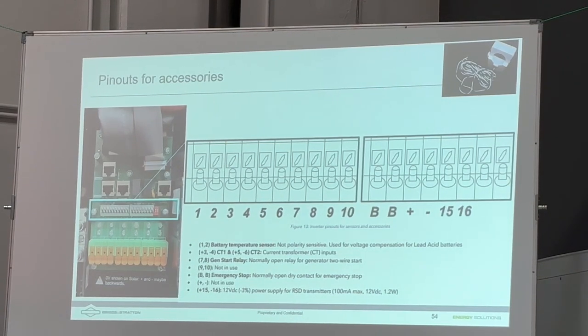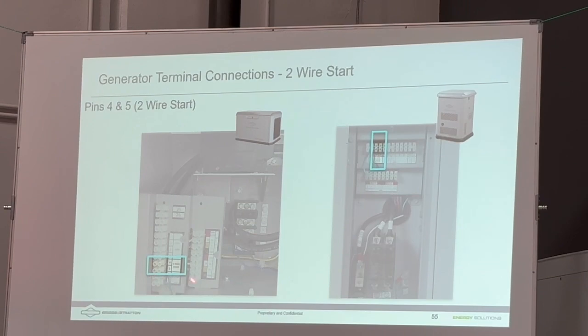Well, the generator itself has a 12-volt signal, at least on the Briggs generators, and whenever these two pins are shorted out, it'll start the generator up. Okay? So we bring those in to pins 4 and 5 in our Briggs and Stratton generators, and anytime the Sol-Ark closes that connection, closes the dry contactor, it'll start up the generator. The generator will start. The Sol-Ark 15K will qualify the signal. Its default, I think, is 60 seconds. And then it'll start passing the generator power in to charge up the batteries and to power loads.